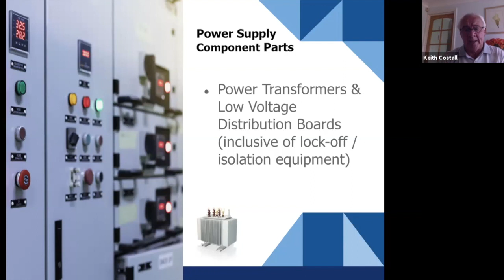Within the substation, once we have that constant voltage electrical supply and need to feed it to the CCRs, we do it through a distribution network. That network needs safe working procedure capability—meaning some kind of lock-off device or isolation equipment. If your substation or vault has been there many years, you may not have that, so you need clear, safe working procedures and processes in place.